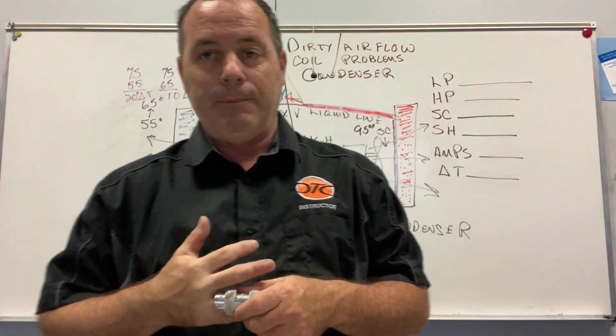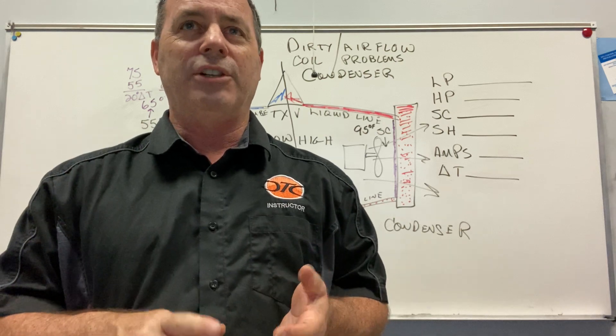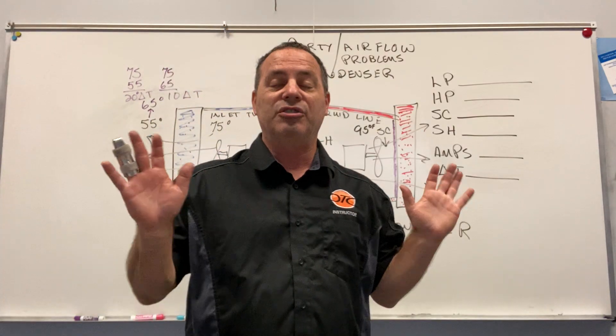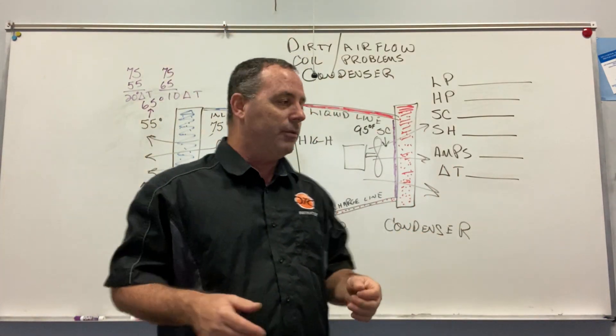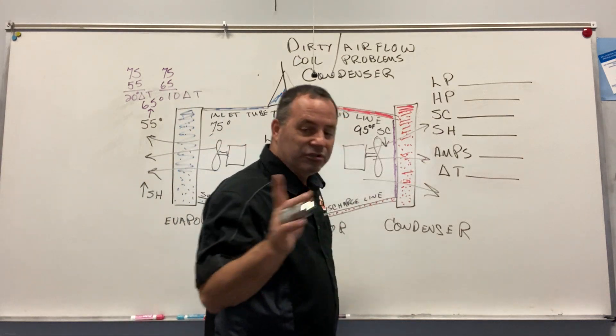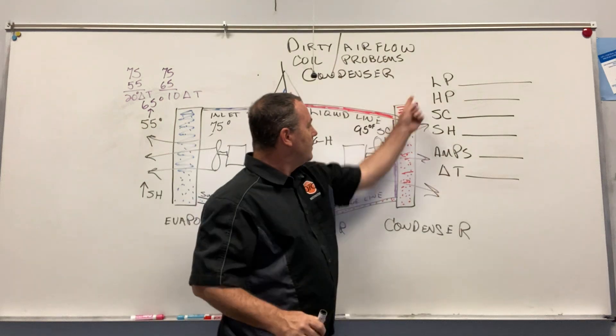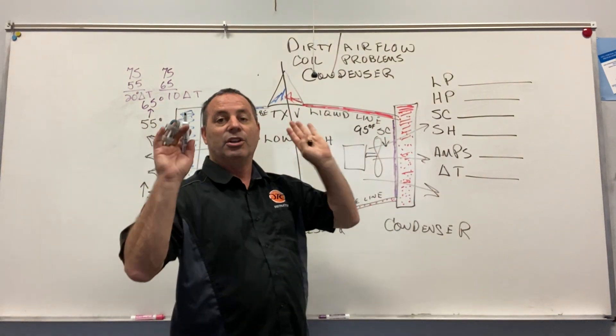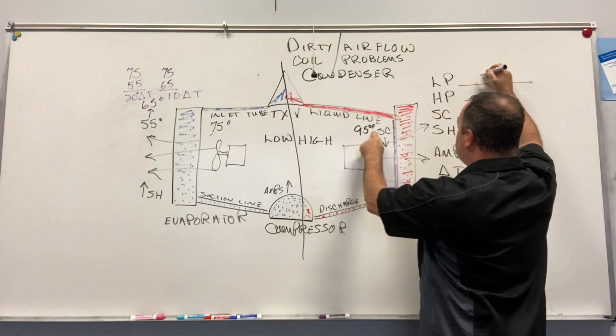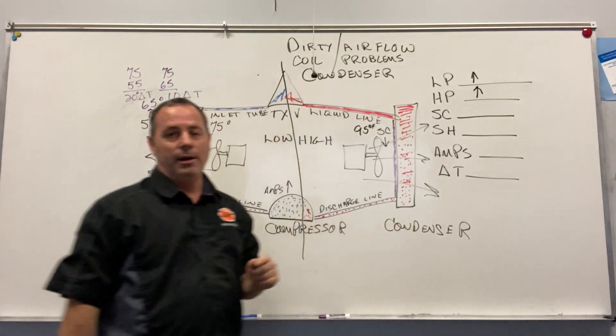Now I'll say high side pressure. It's also called, they call it in the field, head pressure, high side pressure, discharge pressure, high side. I just call it head pressure so you can understand what I'm talking about. So the head pressure and the low side pressure, whenever the head pressure goes up in this condition, the low side pressure also increases. So you'll have head pressure up, low pressure up.